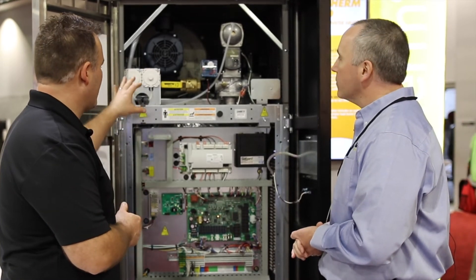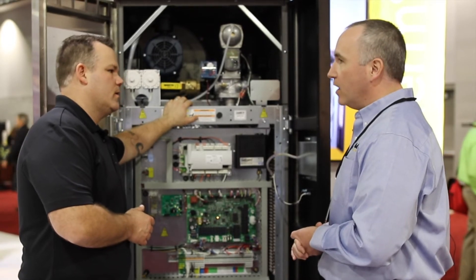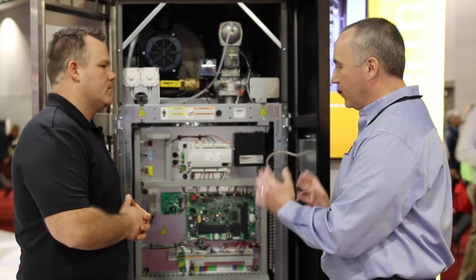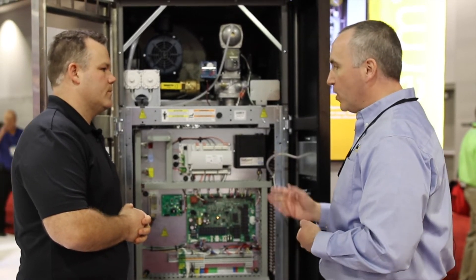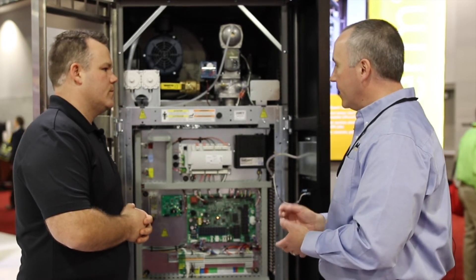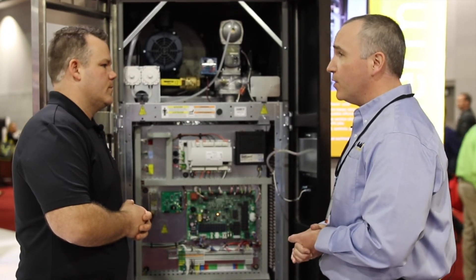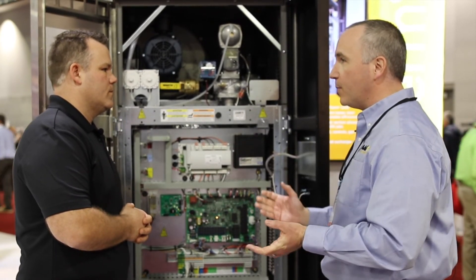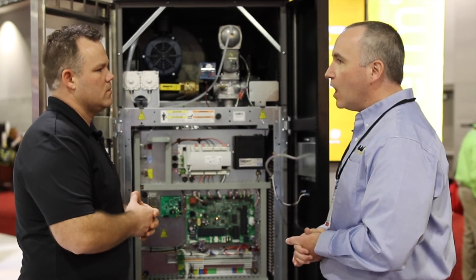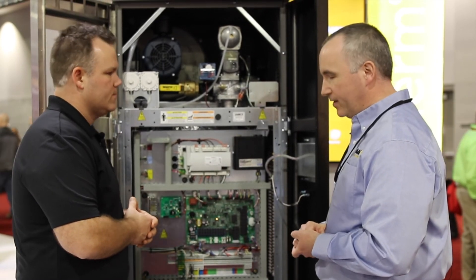You've got some innovative control changes now, but you're using the same heat exchanger. And so that was a decision by us because it's been field proven — a lot of great feedback from the field — boiler or water heater because it's a water tube design. And with the advancements in control, the O2 trim, the high turndown, we think we pretty much have something that can cover most of the applications out there. We're launching this in Q1 of 2019.